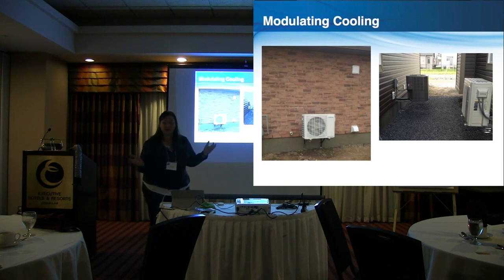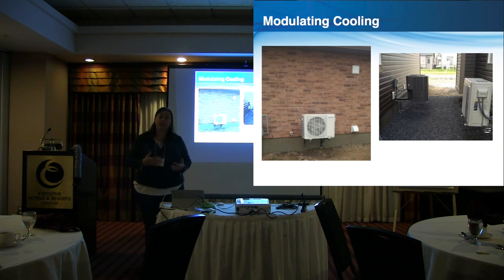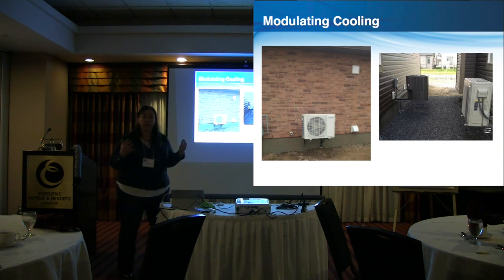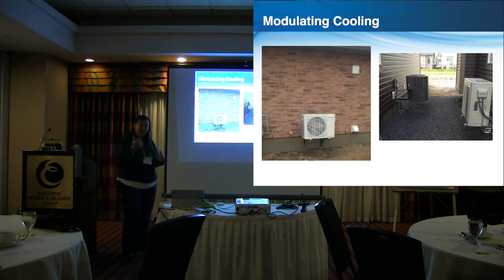They put hundreds of thousands of these things in a year. So we hung our hat on this technology. These things run, same with the furnace, under 50 decibels, which is also really important on the cooling side, because now we've got municipalities saying for spatial separation, you can't put any mechanicals in that spatial separation. We've also got lawnmowers and other issues with spatial separation with traditional air conditioners. So this addresses a few different things from a spatial separation standpoint on noise and space.